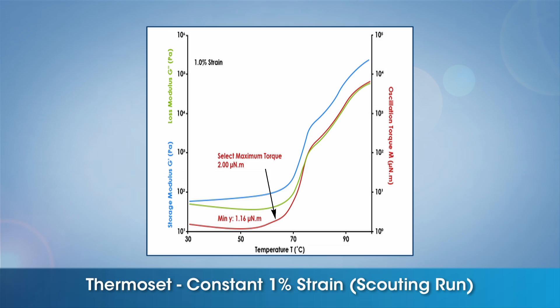From this data, the initial set strain and also the maximum strain was selected to be 1%. The initial ambient torque measured was well within the instrument specifications. The minimum strain was then selected to be well within the linear viscoelastic region of the cured material. The minimum torque is arbitrary in this case since we are already starting at the set maximum strain. The maximum torque, on the other hand, was selected based on the value near the cure onset.